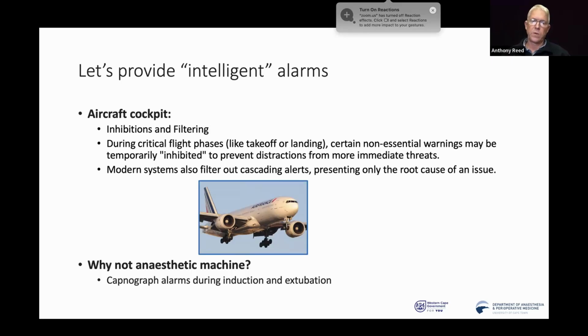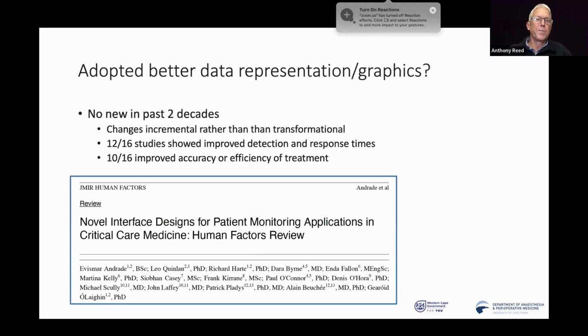And then once we've done that, we connect it up, and then the anesthetic proceeds, and there's a long period where it's really important that you have a disconnect alarm, that the CO2 and the pressure would tell you that. But then at the end of the anesthetic, it's predictable. We need to get those airway devices out. So at some point, we are going to remove them, and the CO2 is going to stop. And every time we do that, the machines tell us that CO2 is not coming out and there's a loss of pressure. And so we have alarms that don't take into account at all what we are busy doing, and they tell us things we know about, and they actually just get in the way. So, I don't know why we haven't changed these things.